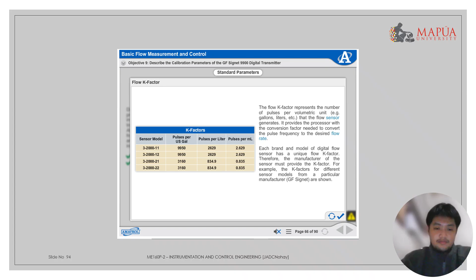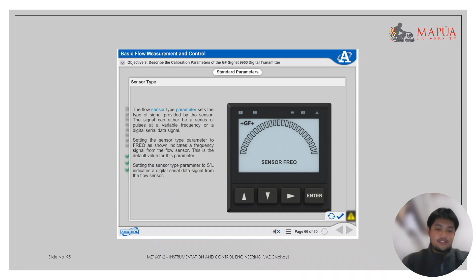The flow sensor type parameter sets the type of signal provided by the sensor. The signal can either be a series of pulses at a variable frequency or a digital serial data signal. Setting the sensor type parameter to FREQ, or frequency, as shown, indicates a frequency signal from the flow sensor. This is the default value for this parameter. Setting the sensor type parameter to S3L indicates a digital serial data signal from the flow sensor.